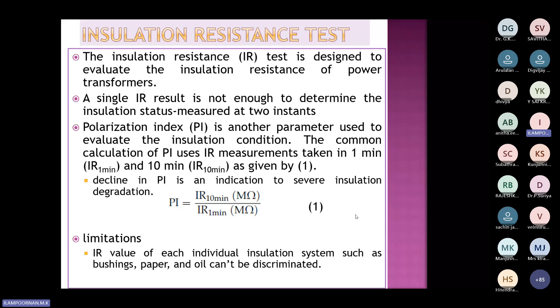Afterwards, the convention came: there is a thing called polarization index. So they found out the ratio between the 10-minute insulation resistance and the 1-minute. Nearer this value to 1, meaning 1-minute resistance and 10-minute resistance are the same, means there is no charging current flow, or it is getting charged in lesser time, that means your insulation is gone. So the higher the ratio, the better. Okay, so that's the idea. Very simple idea, but it actually gives a lot of information about what is happening inside the transformer.